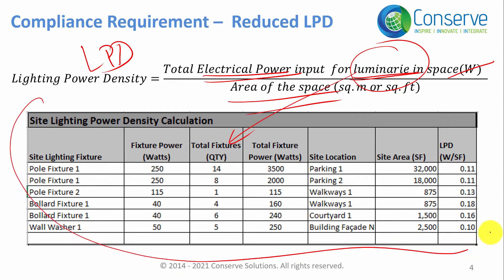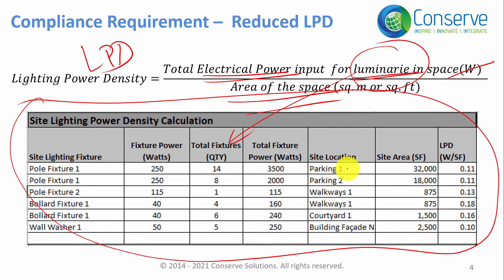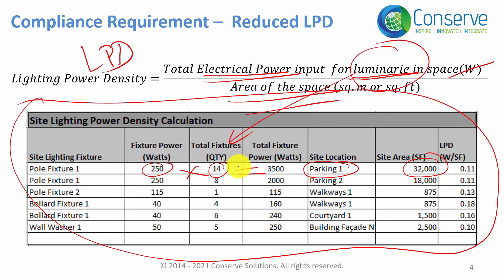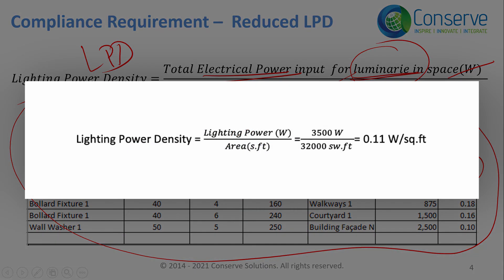Here is an example calculation of Lighting Power Density. Consider Parking One, which has an area of 32,000 square feet and 14 lighting fixtures each of 250 watts. Total electrical power is 250 × 14 = 3,500 watts. The area is 32,000 square feet, so the LPD is 3,500 ÷ 32,000 = approximately 0.11 watts per square foot.